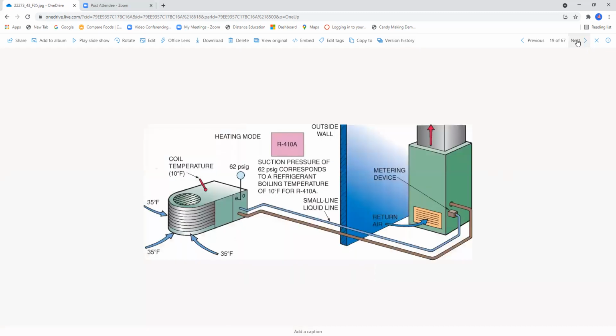Okay, here's an R410A system. Notice that this is in a heating mode. We have 35 degrees coming into the outdoor coil here. The coil temperature is about 10 degrees. We're going to start forming frost at this point. Our low side connection here is going to be 62 psig. The suction pressure, 62 psig, corresponds to a refrigerant boiling temperature of 10 degrees for R410A.